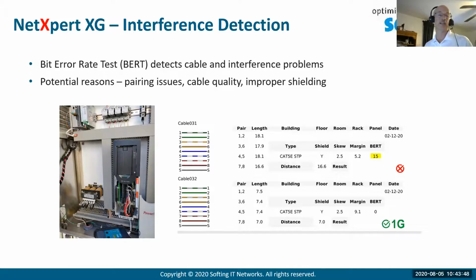It ended up being because of the interference induced in that cable by the drive. So though it was a shielded cable, it wasn't shielded enough. They had to upgrade the grading of the shield and replace that cable, and since then they haven't had any errors.